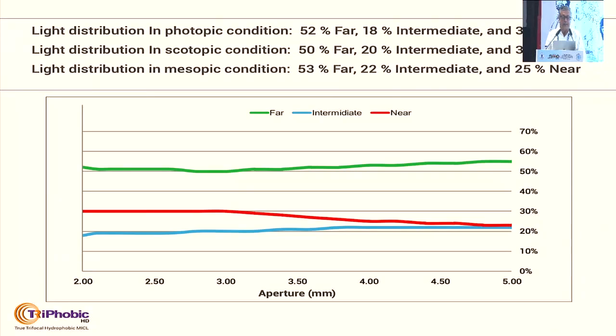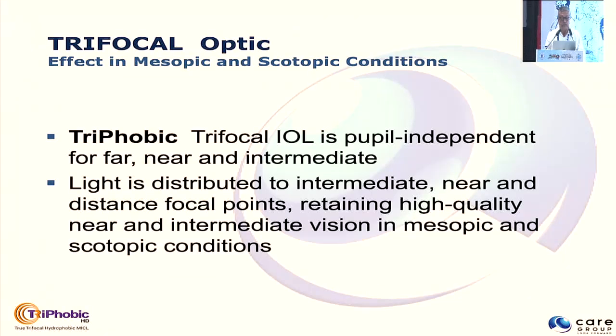It has a unique asymmetric diffractive zone with increasing step angulations and decreasing step height. The light distribution in photopic conditions is 52% for far, 18% intermediate, and 30% near — more or less constant across all pupil sizes. The trifocal IOL is pupil-independent for far, near, and intermediate, distributing light to intermediate, near, and distant focal points, returning high-quality near and intermediate vision in mesopic and scotopic conditions.